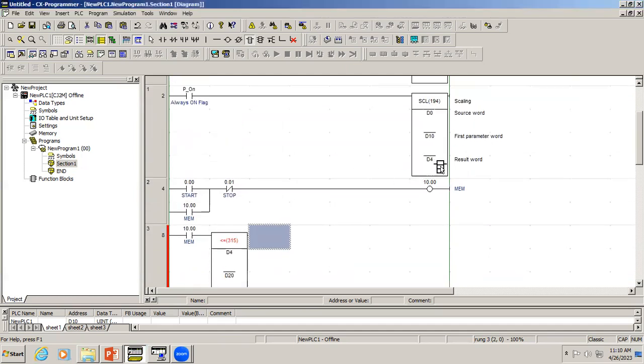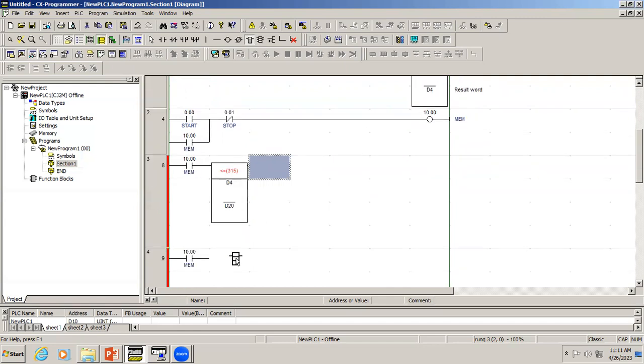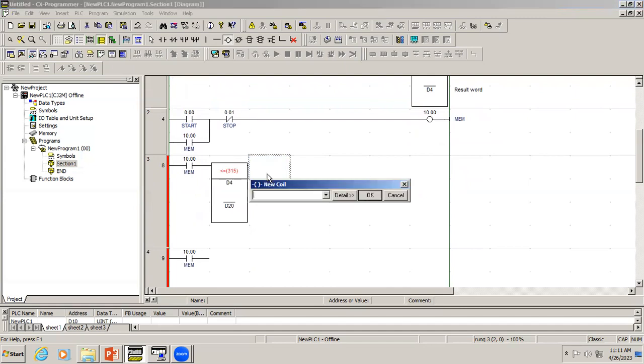D4 will be the result register. As I mentioned in the last video, the PLC resolution is 0 to 32767, but right now we want to see values in terms of 0 to 6000 liters, so that's why we're using the scaling block. The scaled result is stored in D4, and I'm using that register address in the comparator. The set point has been set, and the output here will be the low level indication.